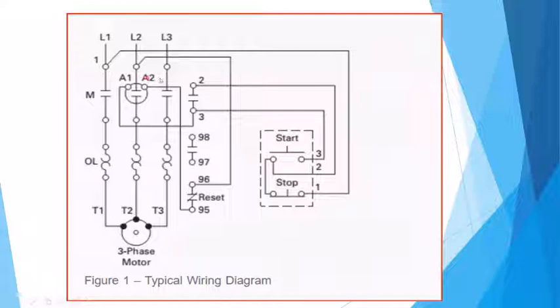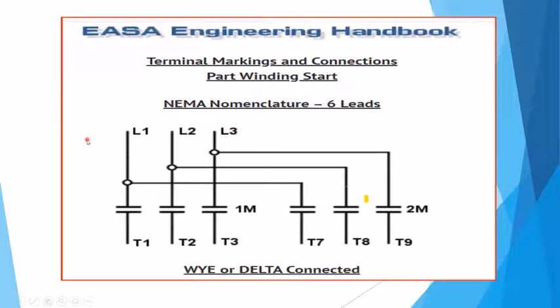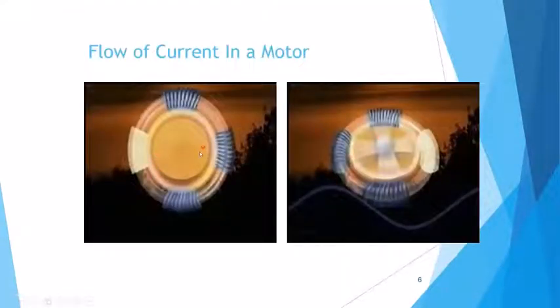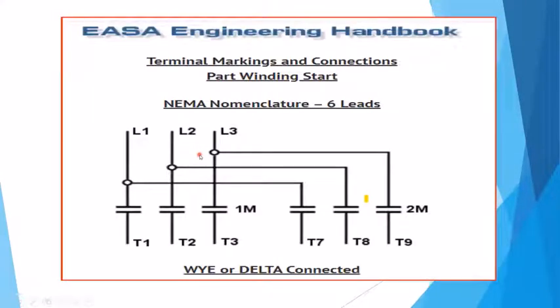So from this, the secondary way they were doing it in soft start, and almost all motors in Europe were done with what they call the Y delta. This is also another way of doing it, where they split up the winding and they do what they call part winding. So what happens is half of the winding is shut off, and it allows the motor to get rotating up to speed. Normally a part winding start will save in inrush current, it will cut it in half. So instead of that 600 amps starting, it'll draw 300 amps just for a period of time till the rotating field gets up to speed. Then with contactors, it brings in the secondary set of windings.